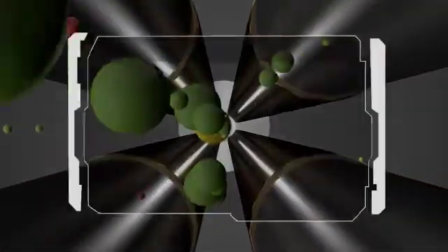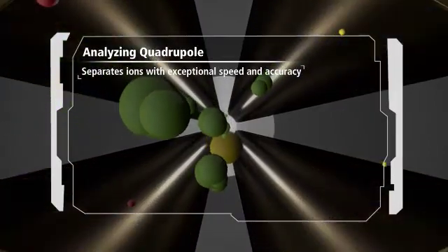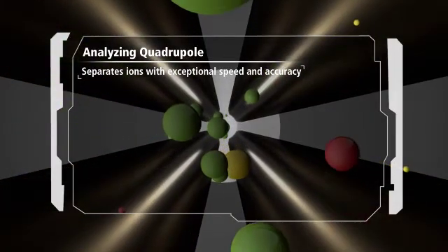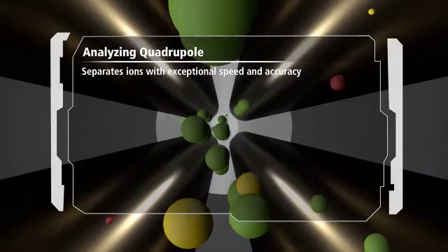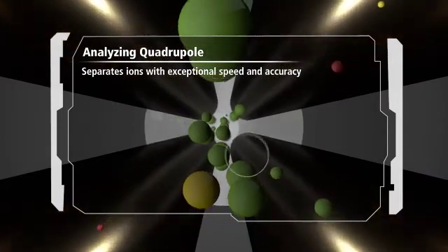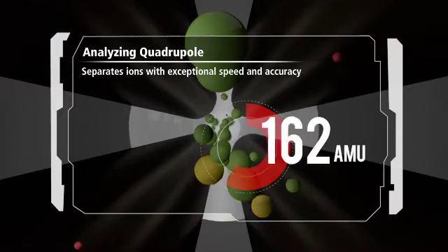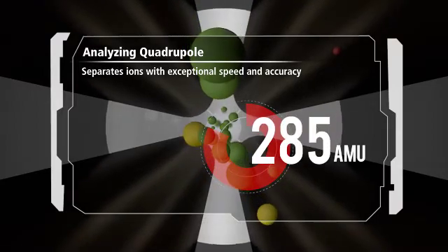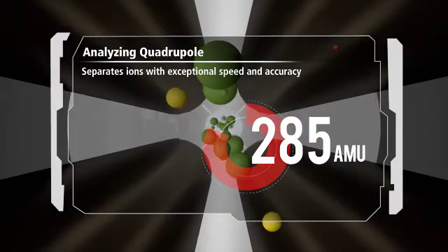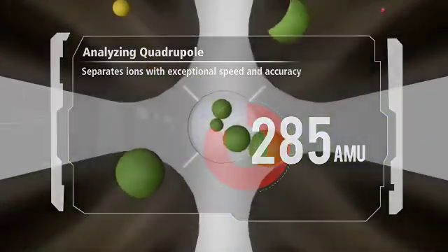With the interference removed, ions are passed into the analyzing quadrupole. Once in, these ions are separated according to their mass to charge ratio. Perkin Elmer's analyzing quadrupole offers the highest analytical mass range available, up to 285 AMU, with exceptionally fast scanning and peak separation.